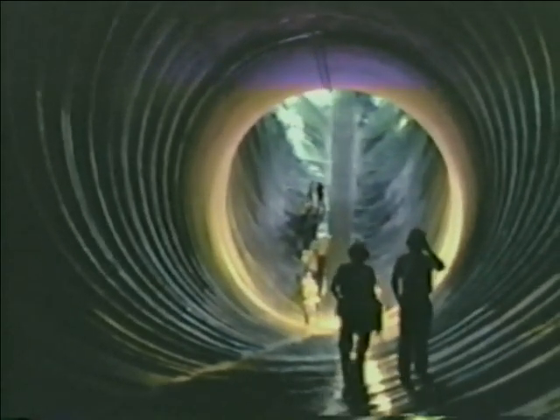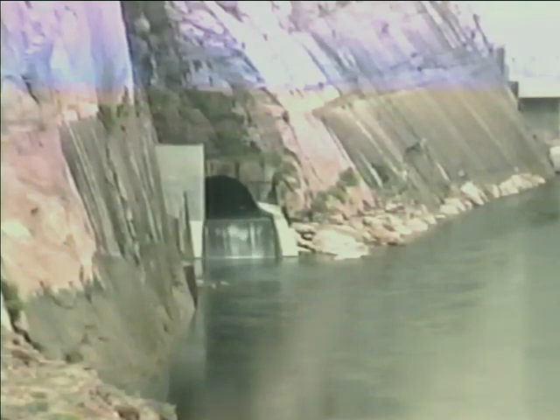After the 5-day test, a team of inspectors entered the spillway tunnel. No cavitation damage could be detected. The design and installation of the air slots had been a complete success. Of course, the spillways will be used again, perhaps not for many years, but when the water again roars down them, the tunnels will be ready.